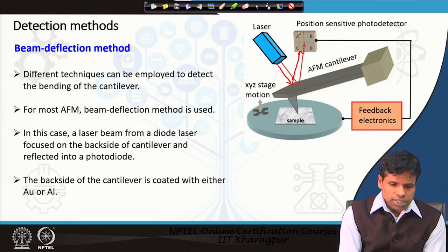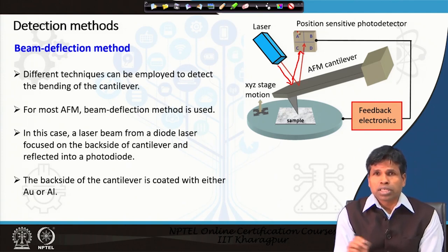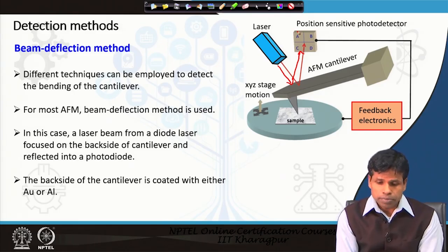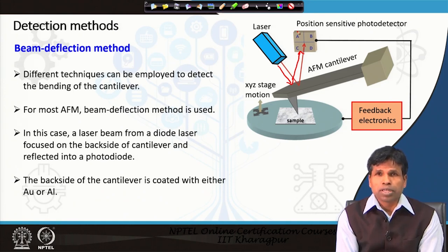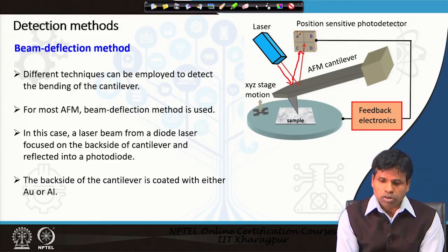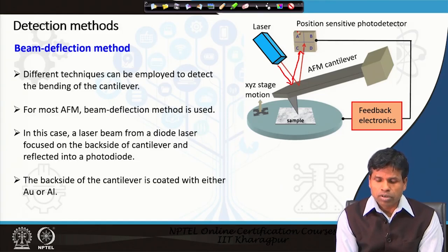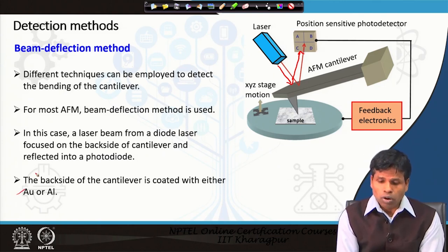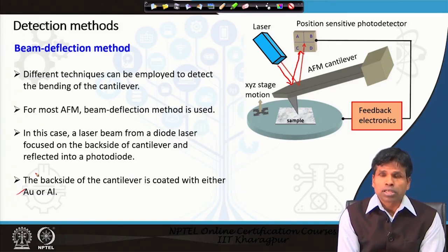In most cases, the backside of the AFM cantilever is coated with a reflective coating, either gold or aluminum. If the AFM is to be operated in a corrosive medium such as KOH or NaOH electrolyte or liquid medium, one must coat the backside with an inert material such as gold. If operated in vacuum or air, aluminum coating can work.